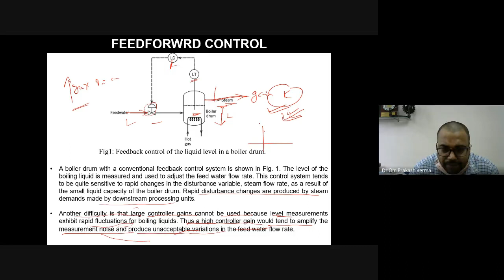Whatever steam is leaving from this tank or from the boiler drum, this is the disturbance for the system. So we are measuring this steam and sending it to this controller. This is the example of feed forward control. The feed forward control scheme in figure 2 can provide better control for this. The steam flow rate is measured, and the feed forward control adjusts the feed water flow rate to balance the steam demand.